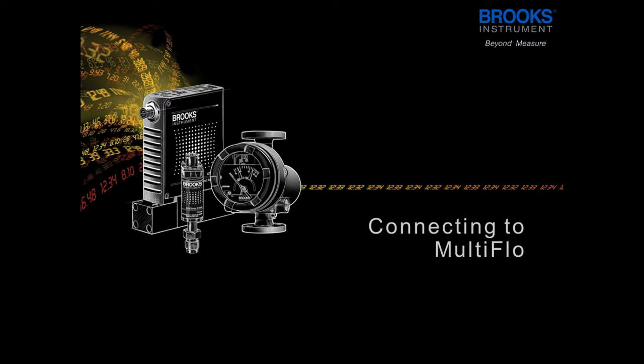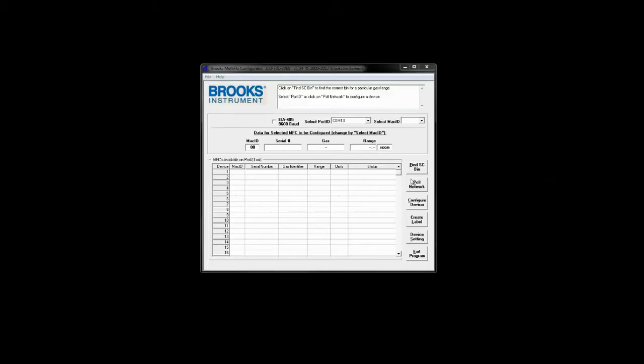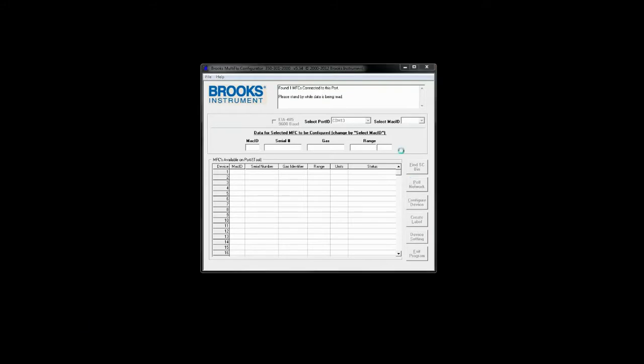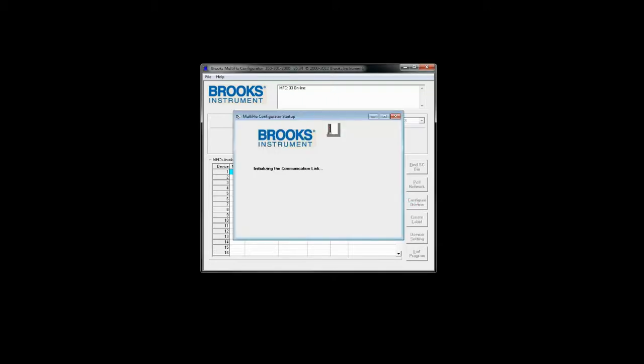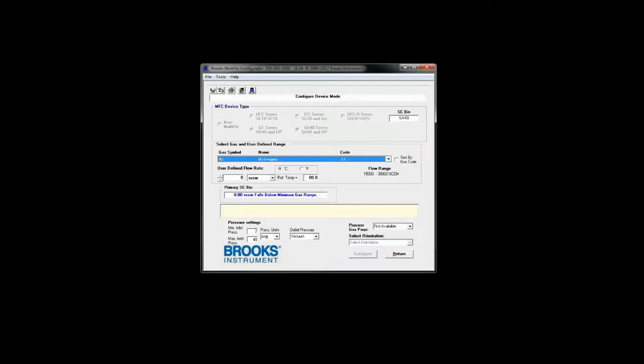Now we're going to go through connecting to a device and configuring it within the MultiFlo program. To connect to a device you will click Poll Network while having the proper com port selected. The connected device will show up in a highlighted line. To edit the configuration of the device you will go into the configure device menu.